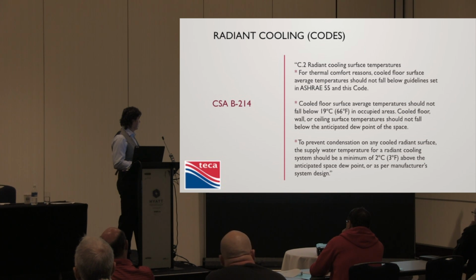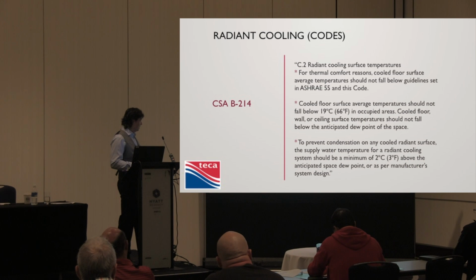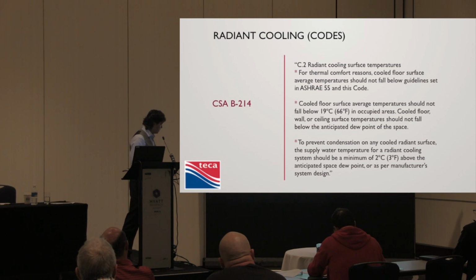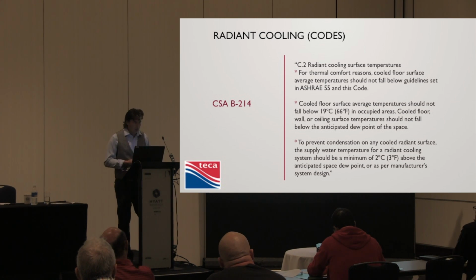Surface temperatures of ASHRAE 55 just refers to ASHRAE 55, 66 in occupied areas. And to prevent condensation, any cooled radiant surface, the supply water temperature for a radiant cooling system should be a minimum of 3 degrees Fahrenheit, 2 degrees C, above the anticipated space dew point as per manufacturer's instructions. Okay, so how do we do that?